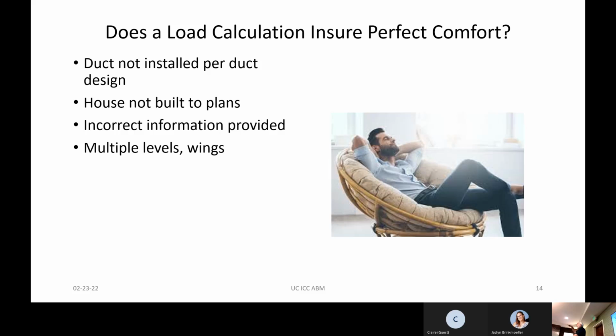We had the most success this way. No one wanted to pay for dampers and zoning, so we put in a 2-stage furnace. In winter, when it was really cold, it ran on the first stage, half capacity, almost all the time, and if it needed extra heat, it jumped to the higher stage. That way we had constant circulation of air. But if you have an oversized furnace that turns on and shuts off, the warm air rises, the cool air drops, and you get a 10 degree difference between the basement and the top level.